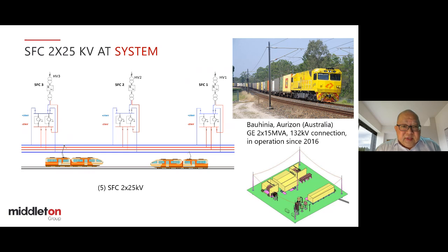And this is the SFC 2x25 kV system using autotransformers. Some of the autotransformers between the SFCs are missing. So what it means is you have 50 kV transmission and you have autotransformer stations in between. That means you can feed much further than the 1x25 kV system. So it has all the benefits of the classic autotransformer systems, and I reckon the EMC is as good or better than the classic AT system, as train current is actually fed from both directions, so you don't have the full current coming from one direction.